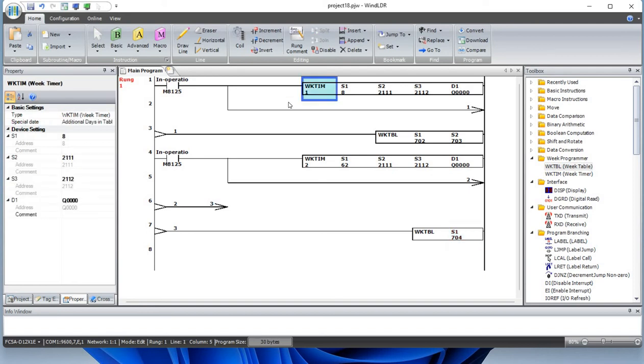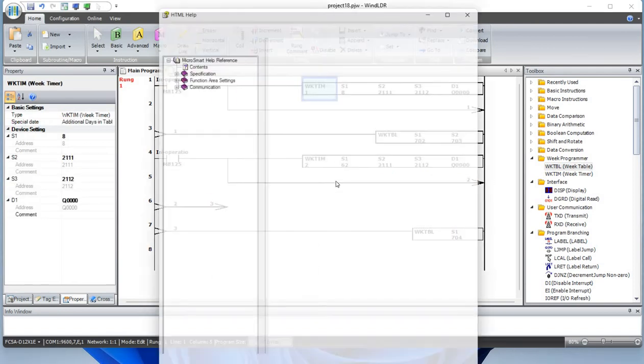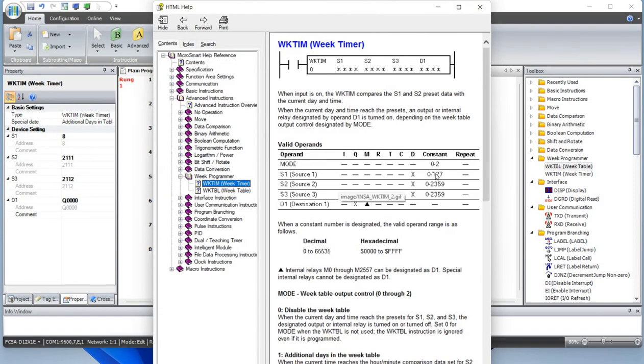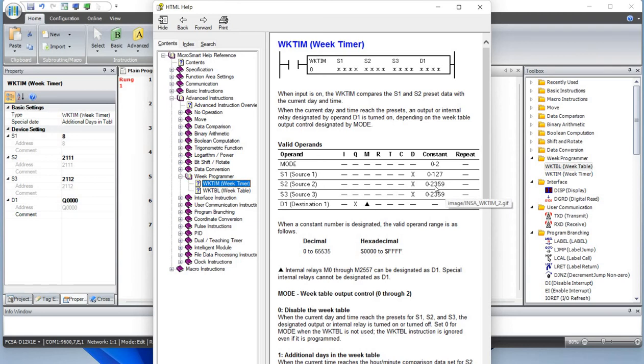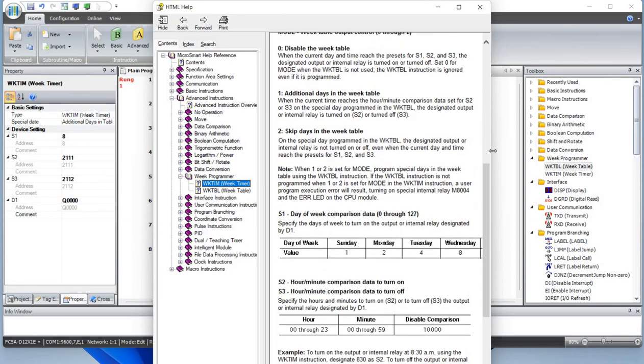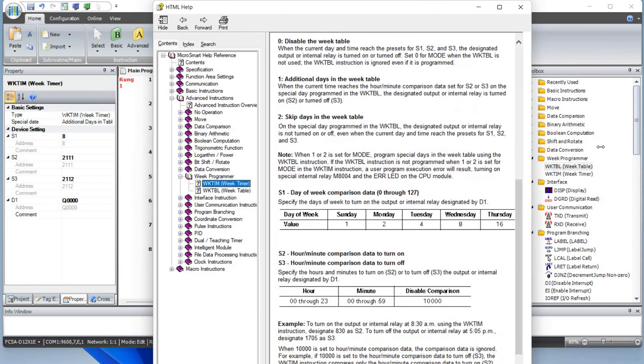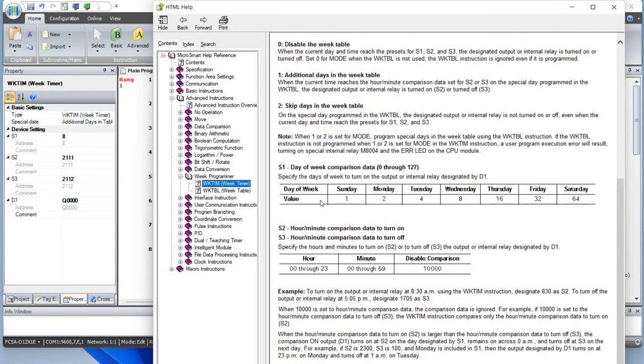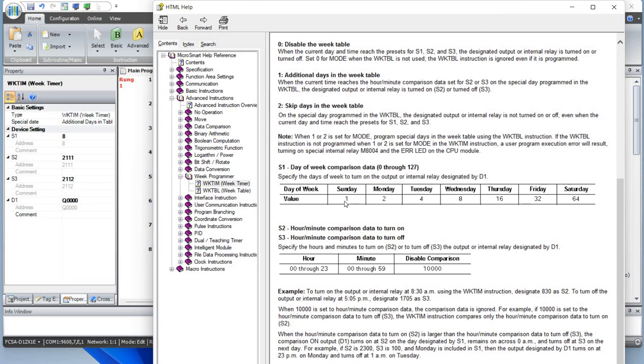I want to go over the help function. The mode would be zero, one, and two. S1 would be zero to 127. This would be on time, up to 0 to 23:59, and off time would be the same. How do you know S1? It's 1, 2, 4, 8, 16, 32, or 64. If you are working on Saturday and Sunday, that would be 1 plus 64, which is 65.